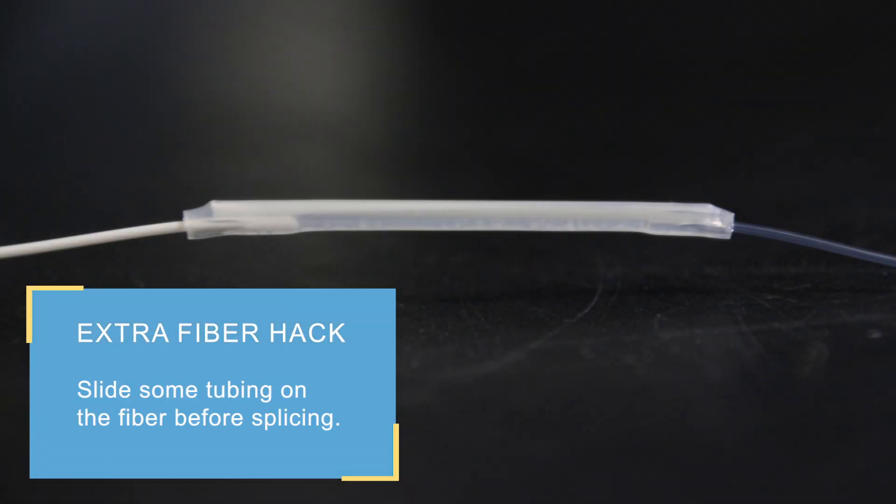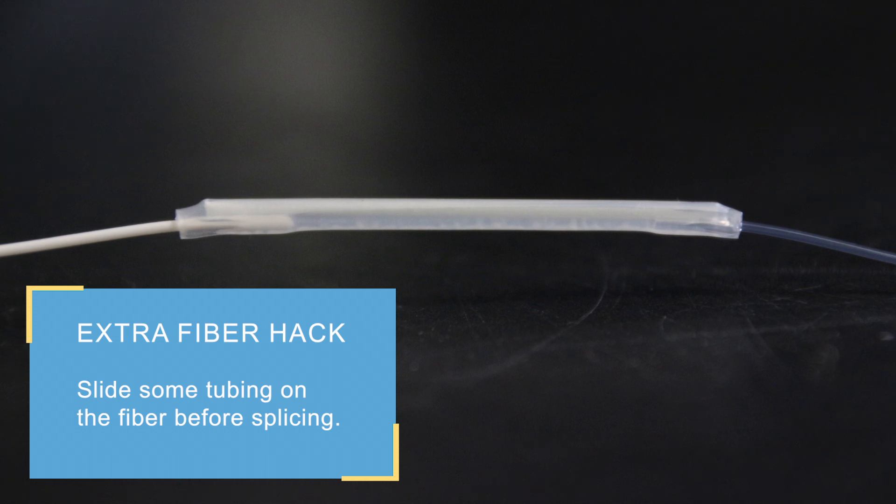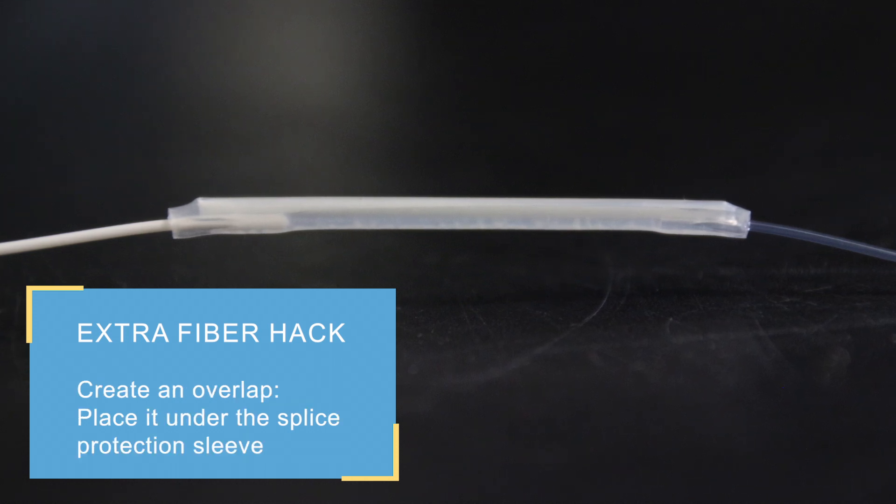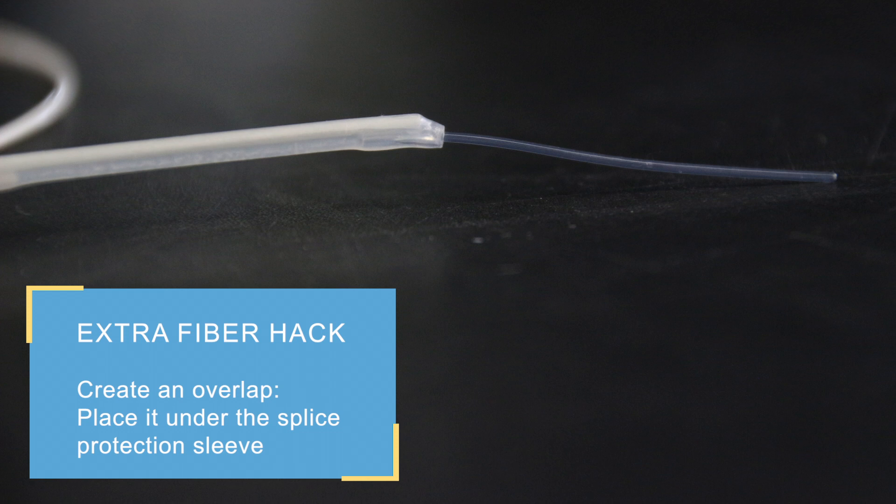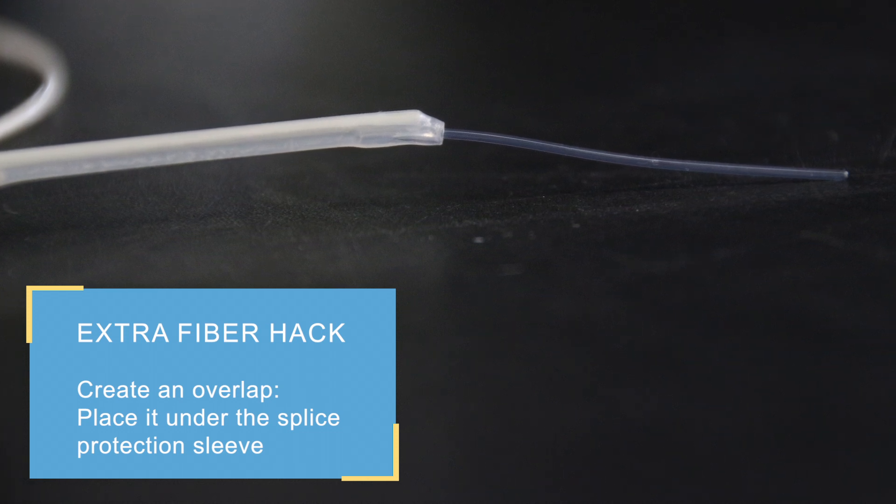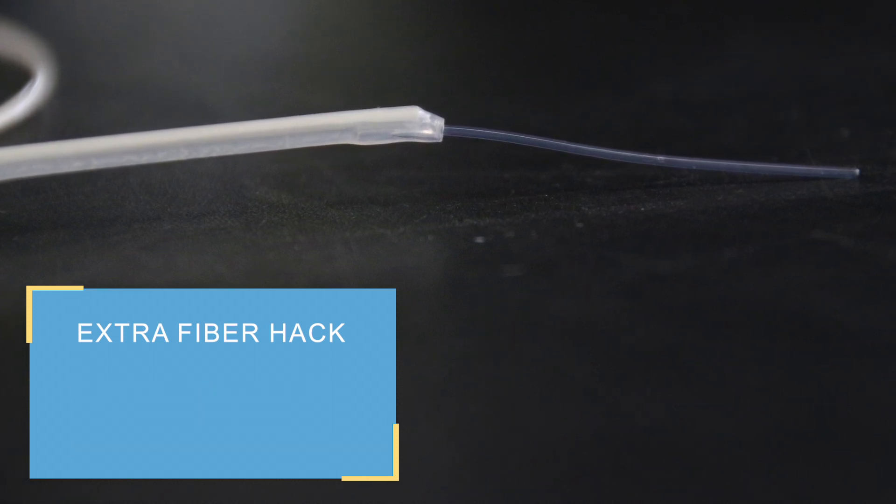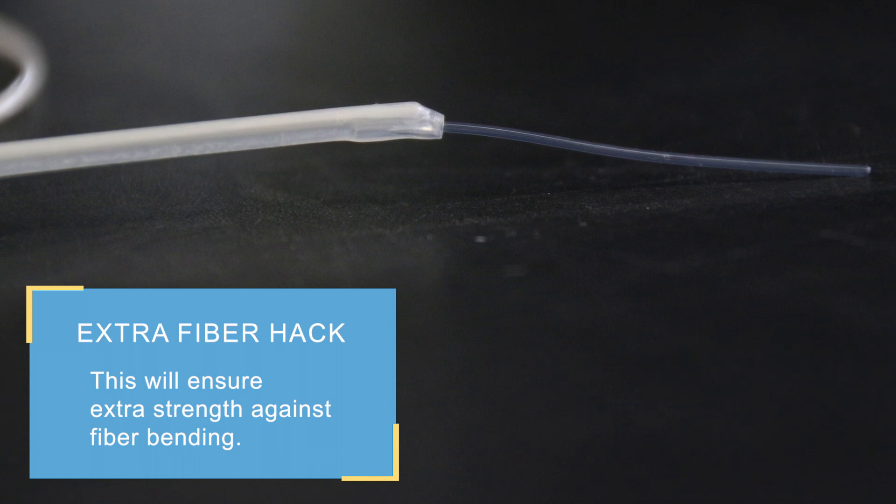Our fiber hack: slide some tubing on the fiber before cleaving or splicing. Place it a few millimeters under the splice protection sleeve to create an overlap. Then proceed to the heating. This will ensure extra strength against fiber bending.